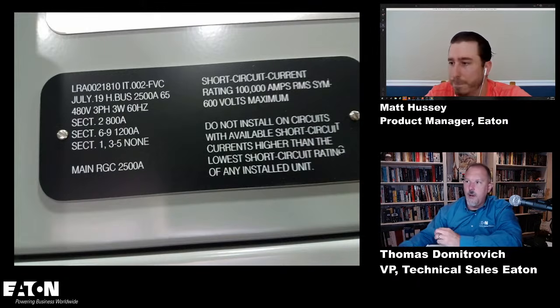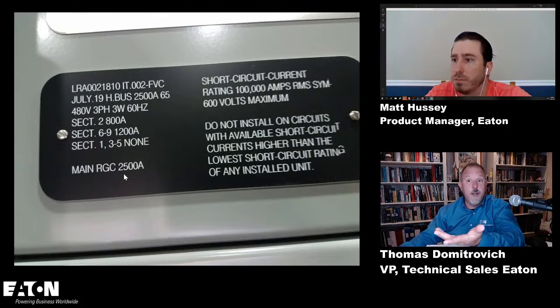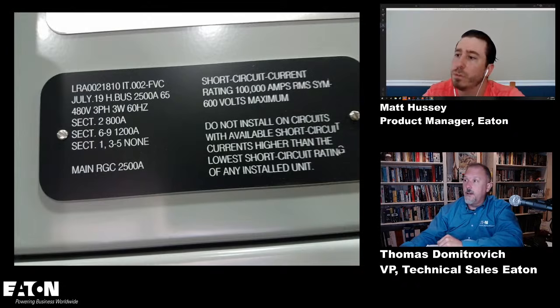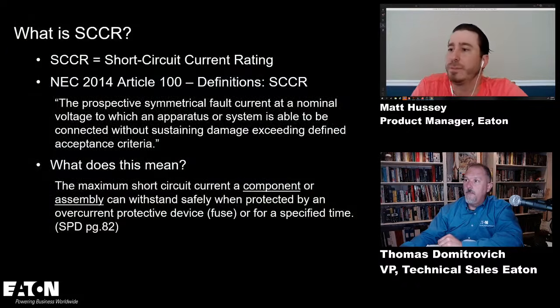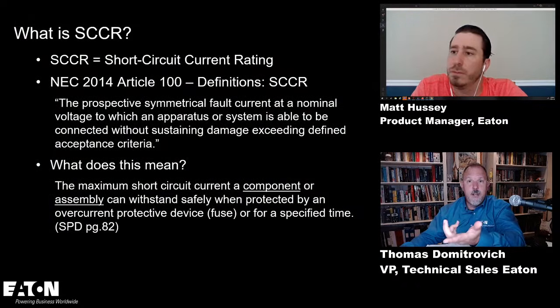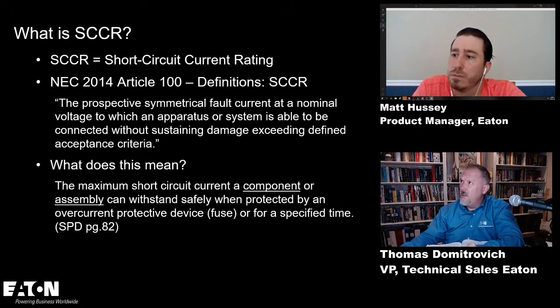It's got a main RGC, which RGC is the breaker. So that's specific to us, an RG type breaker, right. R frame. And that means that it would have an arc reduction maintenance switch on it. It would have ground fault protection of equipment. No. Yeah, right? If it was service entrance. If it was service entrance, yeah.